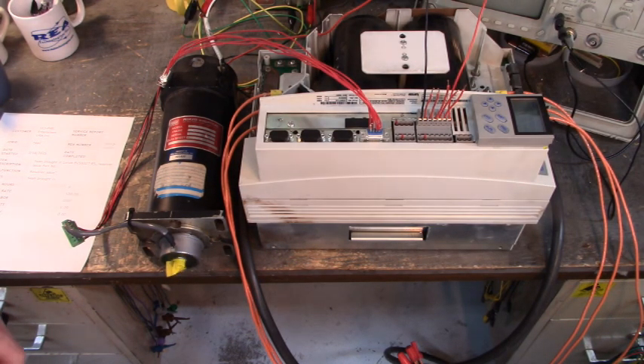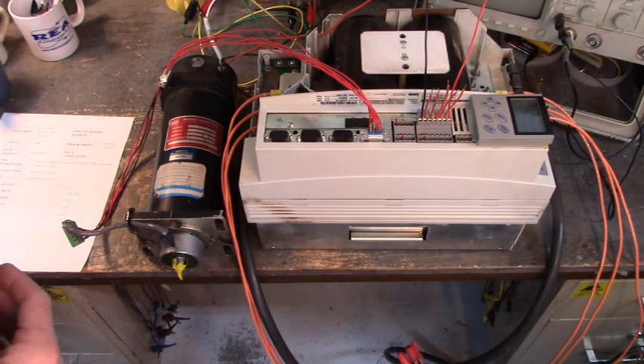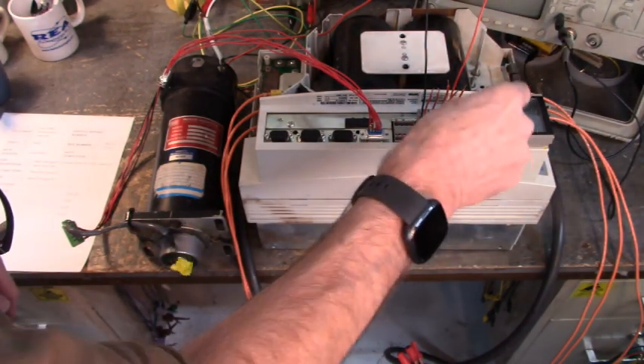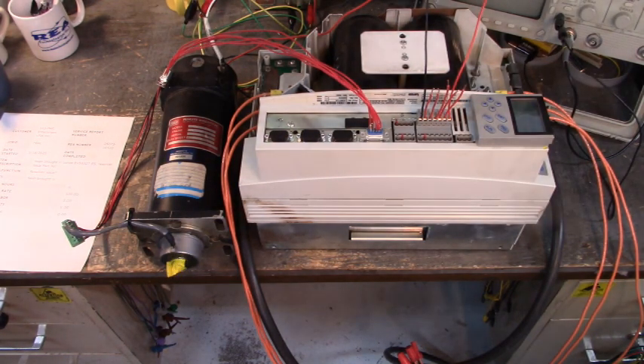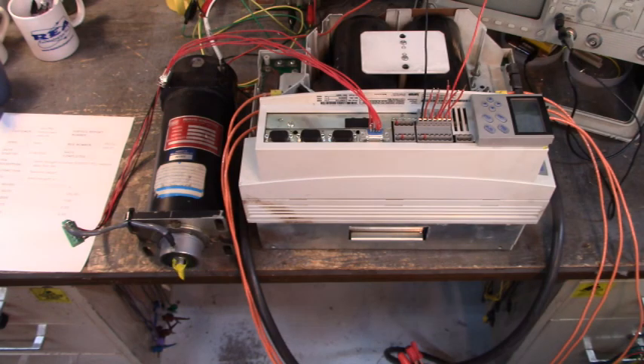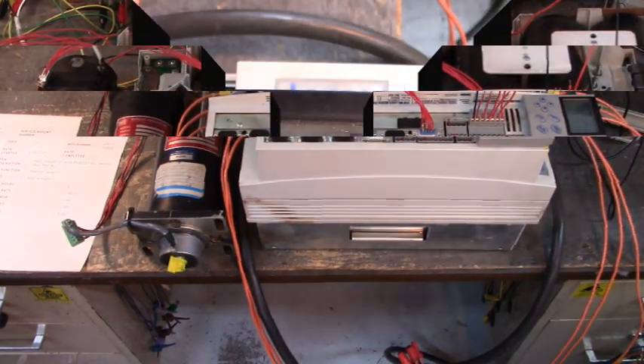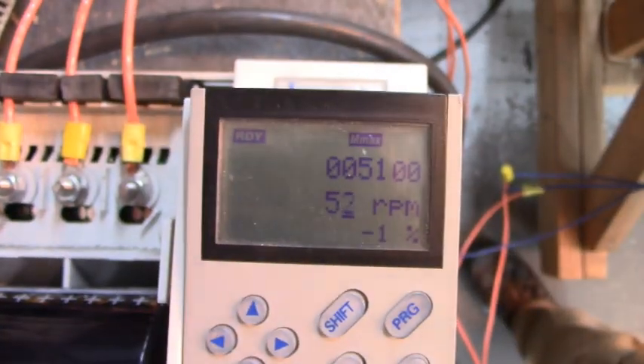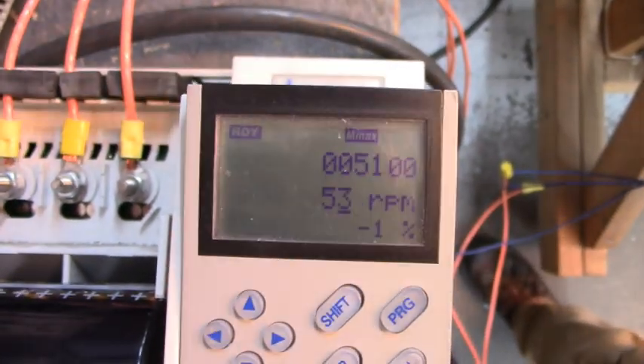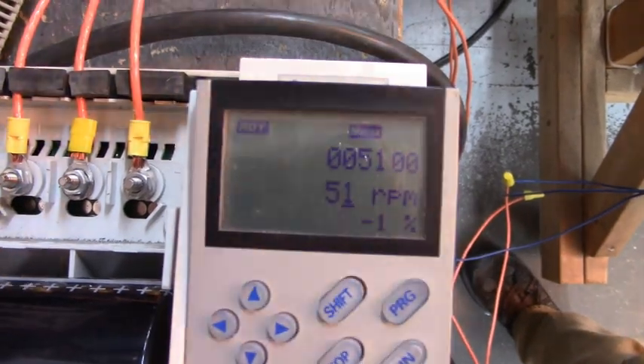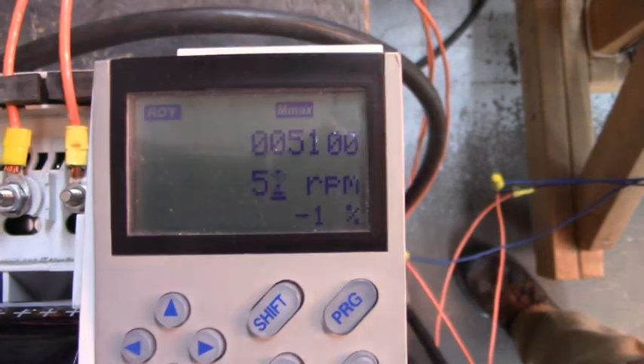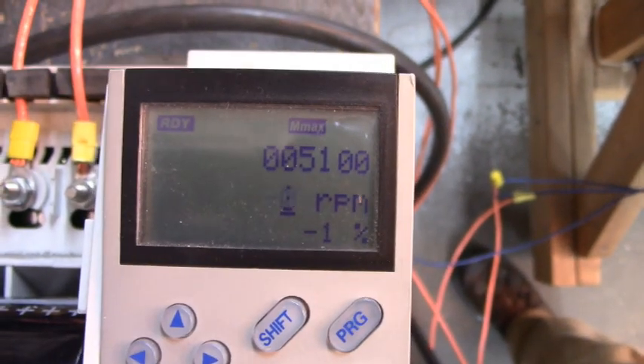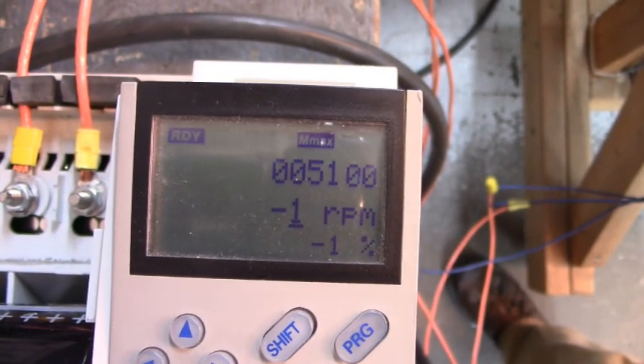I'm going to hold the movie camera and put it in front of that display. So y'all can see what that display is doing. There's the RPMs from the feedback. From the resolver feedback. I'm going to stop the DC motor that's rotating that resolver. And you can see the RPMs go to zero.